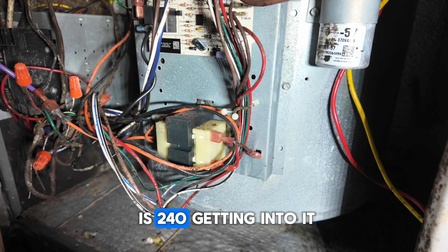That is a direct drive motor. There's no control, it's not an ECM, electronically controlled motor. It runs when there is 240 getting into it. So this is just a switch. This one is connected directly. This one is like a switch now. This switch is to send in 120 volt to complete the electrical circuit, which is 240 volt for this motor to run. So that is why they don't need this one, right?